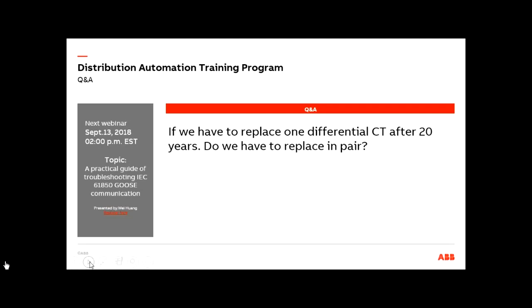If we have to replace one differential CT after 20 years, do we have to replace it in pair? Great question. The requirement for differential protection to operate accurately is that the CTs should feed the same current. It is always recommended to get the differential CTs from the same vendor with the same turns ratio. If you are replacing, it does not mean that you can get an accurate CT after 20 years, but one has to make a careful study of the existing CT on one side and the characteristics of the CTs you're buying after 20 years.